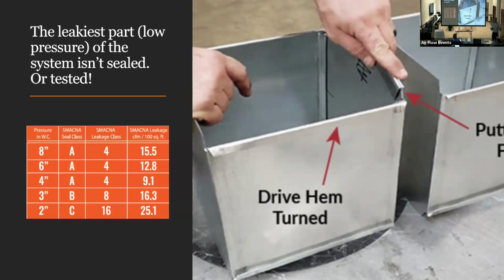I mean, think about just the fan law. 0.9 cubed is the horsepower penalty. That's not good. And then all the air conditioning, filtering, heating, dehumidification that you accomplished, you just threw it into the plenum. Okay, well, we've covered this. So if we get to this 25.1 number, bingo, yes.